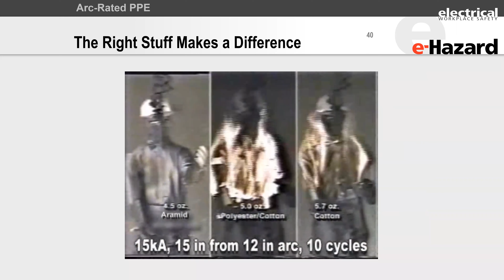Cotton, polycotton, there is a slight difference in the survivability, but the survivability of arc rated materials, in this case an aramid, is dramatically different. Almost everybody I've investigated, even if they weren't matched to the hazard, even if they weren't wearing exactly the right PPE, they lived when they were wearing arc-rated materials. And about 50% of the time, you expect to have a person die if they're wearing non-arc-rated materials or be badly hurt.